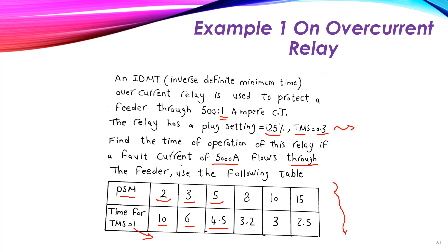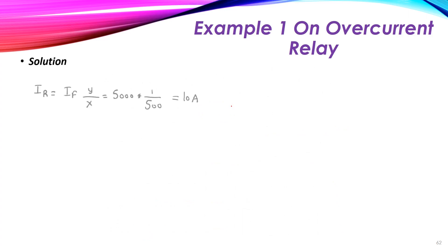We have a fault current of 5000 amperes. This fault current is first seen by the CT, which steps it down from 5000 to a certain value. The current flowing through the relay equals the fault current multiplied by the CT ratio: 5000 multiplied by (1/500) equals 10 amperes. So the fault current at the relay side is 10 amperes.